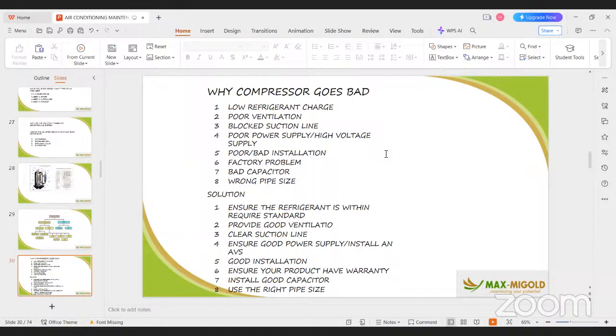Then poor power supply, which happens to be a problem in Nigeria. I will also give you people advice here. What advice am I giving you? If you want to buy an AC in an environment where there's not much power, I will advise you to go for single phase AC. Don't go for 3-phase. Because sometimes when PHCN takes their light, what happens? 2-phase or 1-phase might go. The AC that is working on 3-phase will not come on. But all your single phase ACs will be on and running. So you need to look at this when you are selecting your AC.